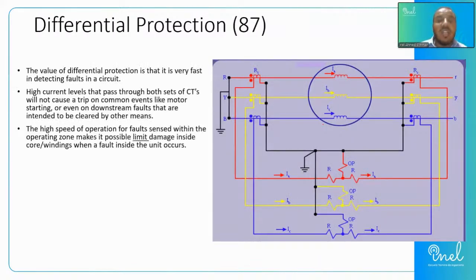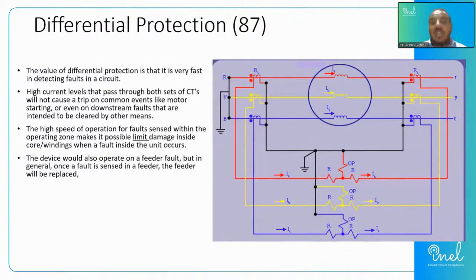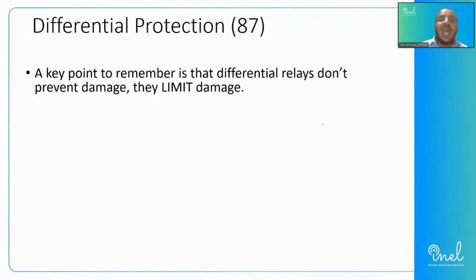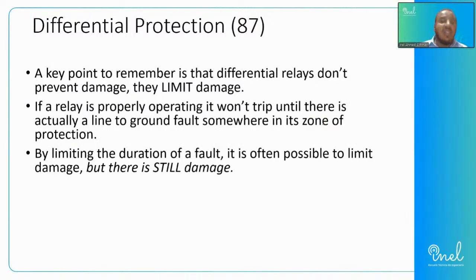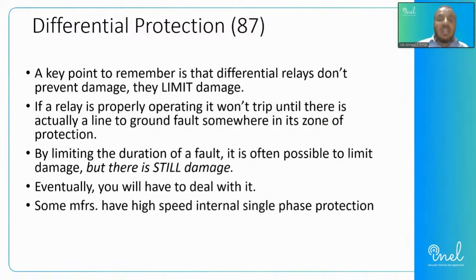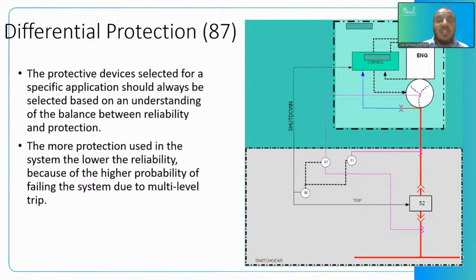So we have differential relay 87, and it would act based on the difference of the current between the phases. We can put some differential protection on the line and some differential protection on the ground. And from here, 87 would act to protect against the differential current and to limit the duration and the risk of any difference current that may appear between phases or between both sides, primary and secondary, within the protected area. So we have the differential protection devices which act on the difference here.